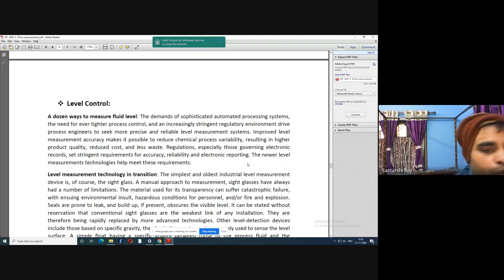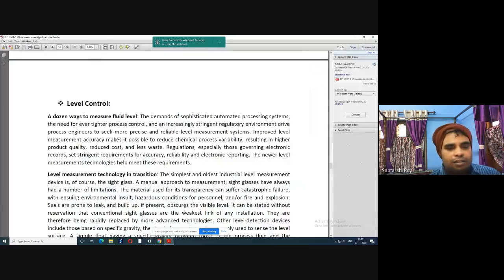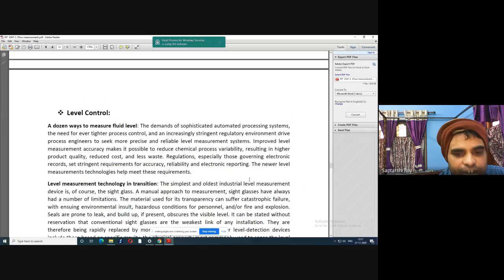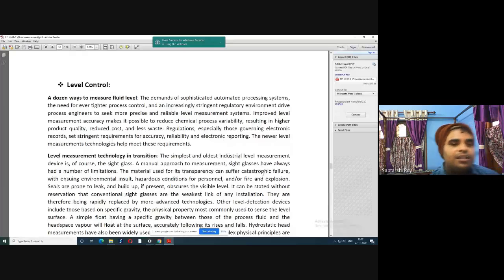The simplest and oldest industrial level measurement device, of course, is the sight glass. A manual approach to measurement, sight glasses have always had a number of limitations. The material used for its transparency can suffer catastrophic failure, with ensuing environmental insult, hazardous conditions for personnel, and/or fire and explosion. Seals are prone to leak and build up, which, if present, obscures the visible level.